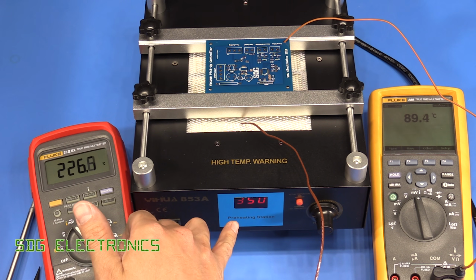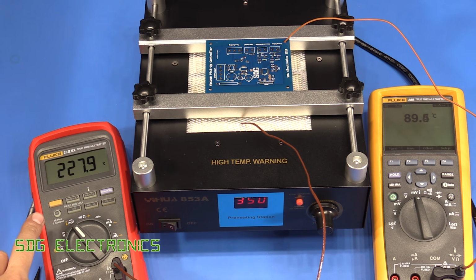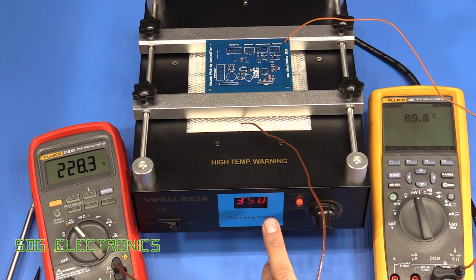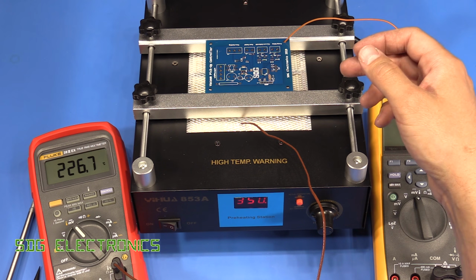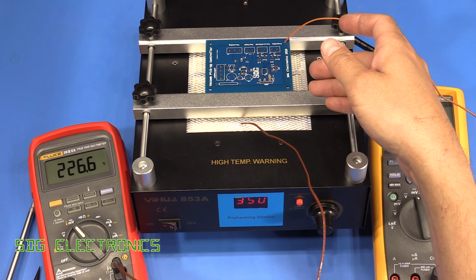Right, so the device says it's up to 350 degrees, but the thermocouple that's on the plate isn't anywhere near that. And interestingly, the hot plate isn't actually that active. You can see the little dot on the front panel which is saying when the hot plate is actually turned on, and it's not doing 100% duty cycle. So there is more heating capacity available.